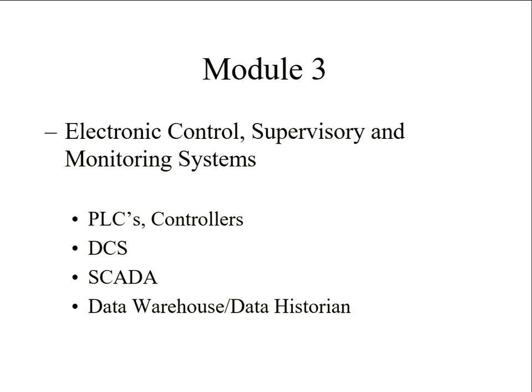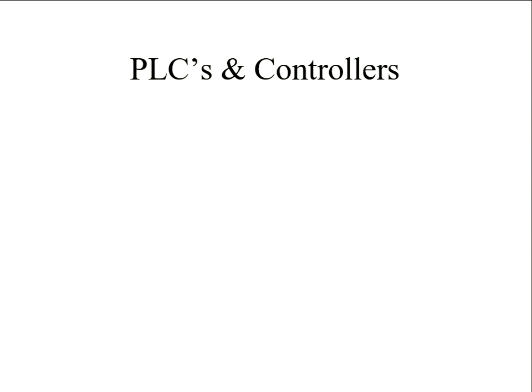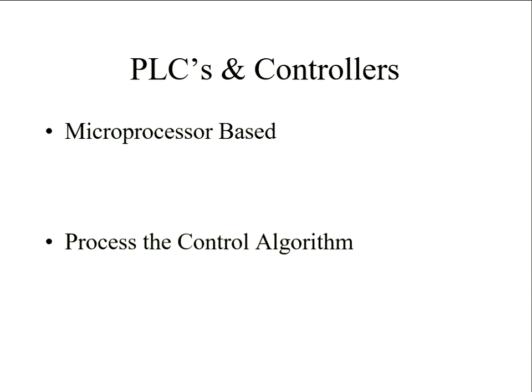So when I did an LNG vaporizer control, at first they said they wanted a nice continuous control. Once it's on, we want it to control the throughput and the gas temperature. Once they said it can do that, we want it to do the startup as well. So that's more of a batch type thing. Switch this, followed by this, then bring this on. As it so happened, the unit we were using was able to do some sequential control as well as straight PI control. So continuous control is the type we're talking about, the PIs.